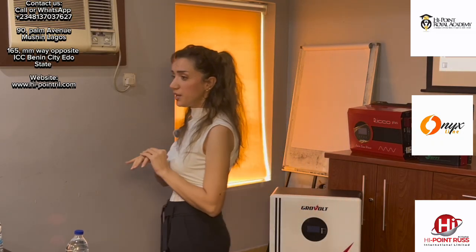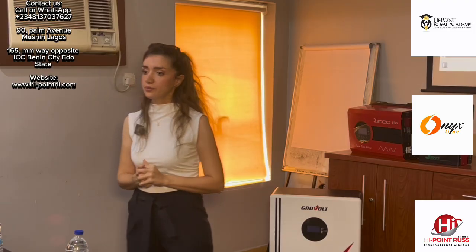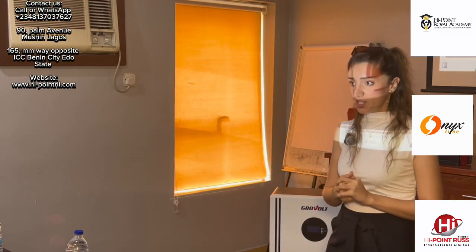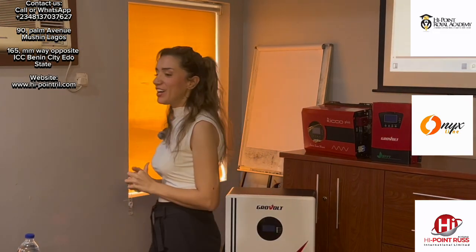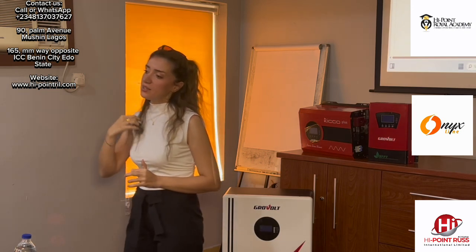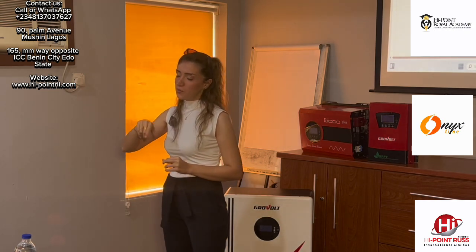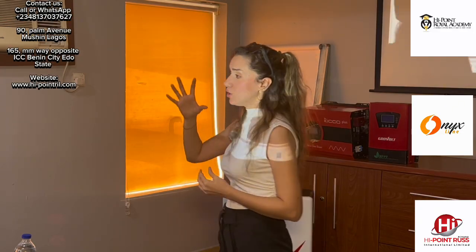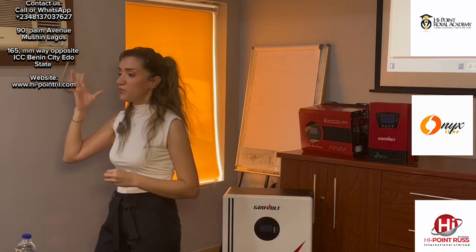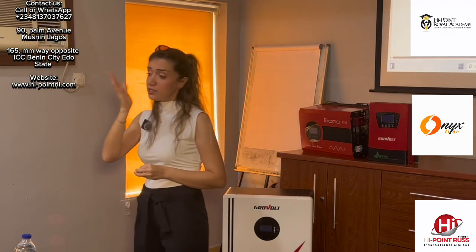6,000 cycles and the DOD. What's the meaning of DOD? Depth of discharge. Yes, that means the 6,000 cycles. When you mention the cycles of your battery, you have to relate this cycle to the DOD. So, 6,000 cycles at DOD 95.